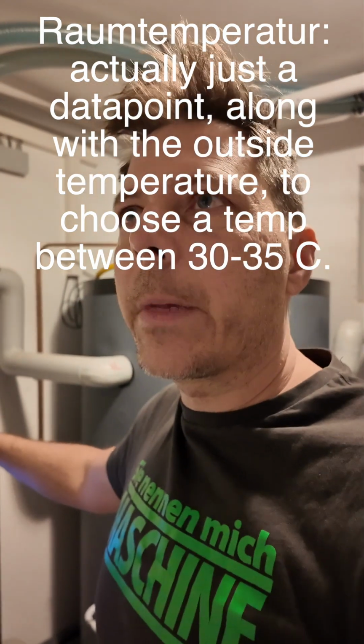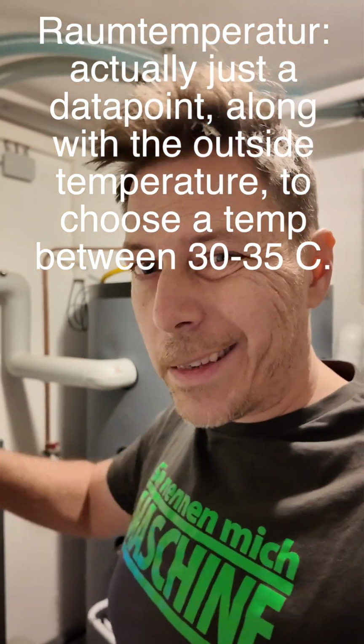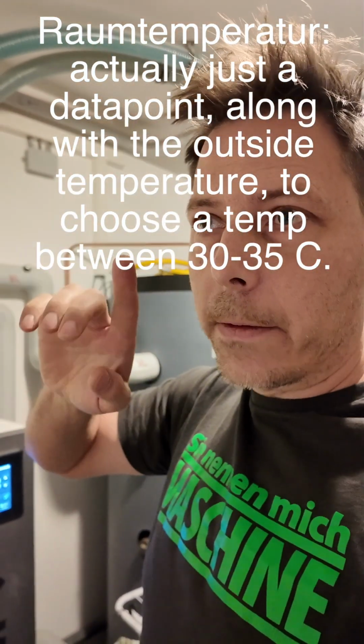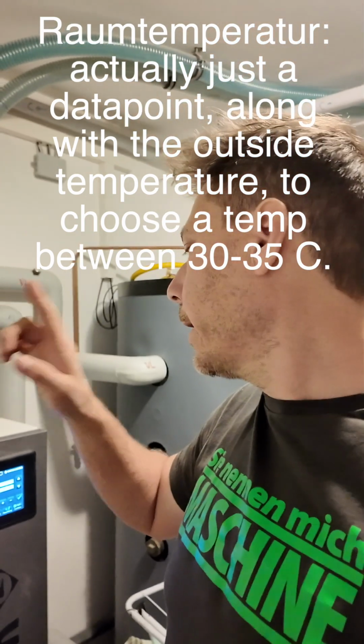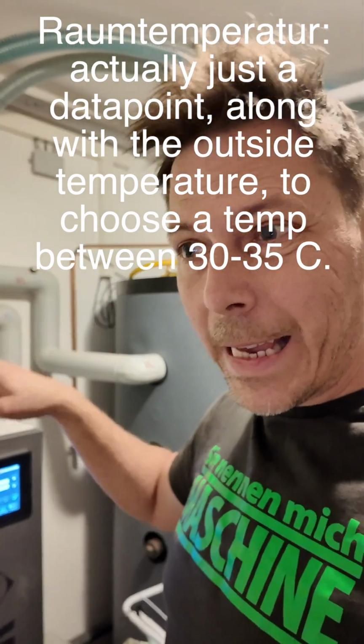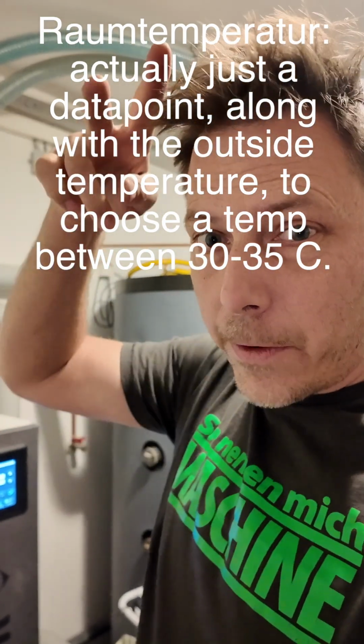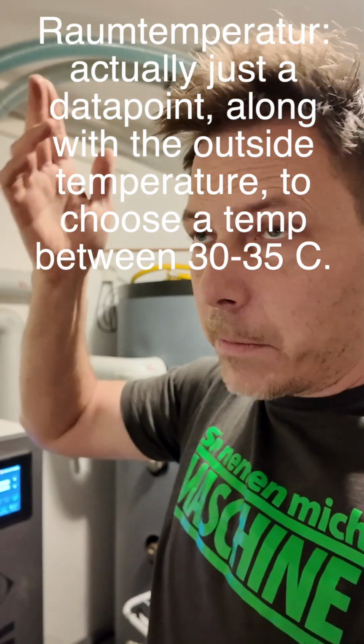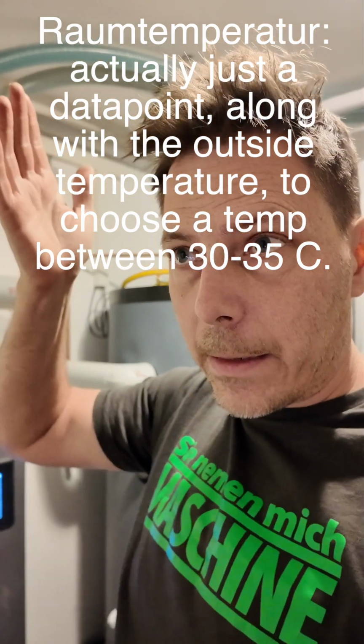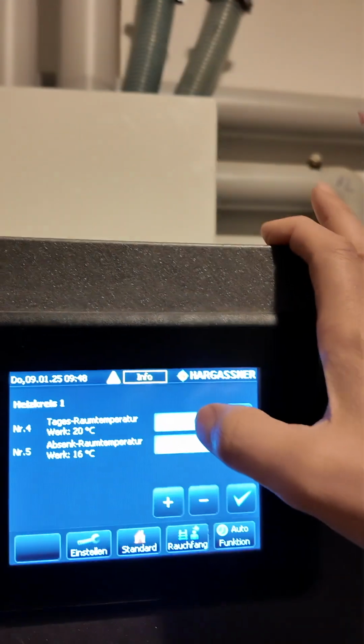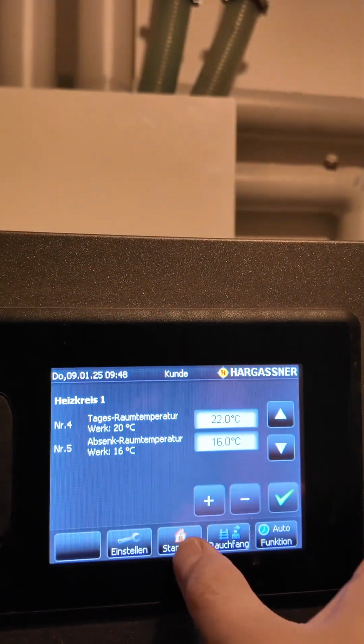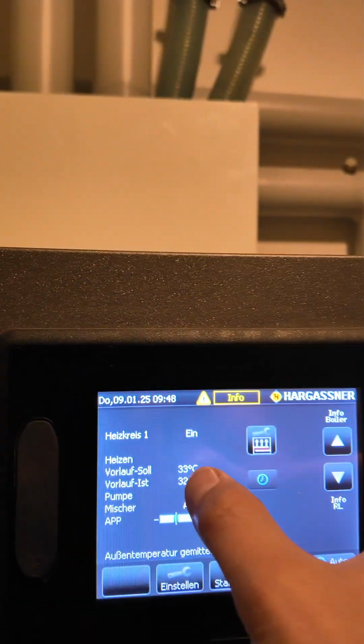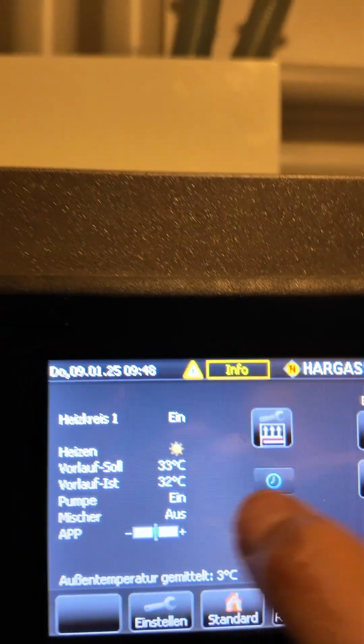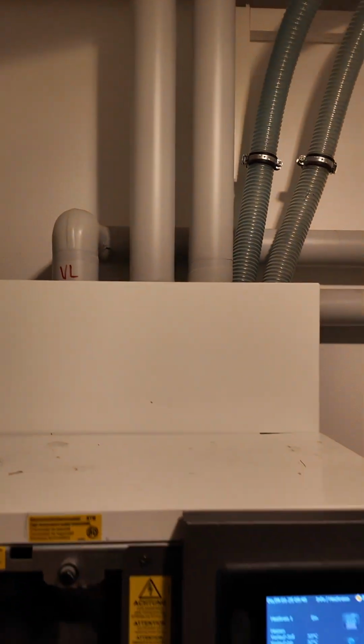Instead, what it is, it references a diagram where they consider the outside temperature, they consider the set point of 22 degrees, and they actually send something higher than that, like anywhere between 30 and 35 degrees Celsius into the Heizkreis, or the heating circuit. So in this case, if we set up 22 degrees, then what it's going to actually aim for is 33 degrees Celsius to get sent up into the floors.